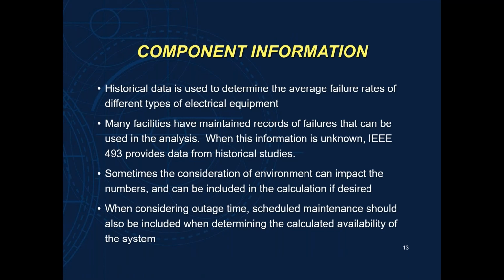Some bigger companies and companies that have a lot of records of their maintenance and their failures will have their own failure rates, say based on a circuit breaker. If they say it's a medium voltage circuit breaker, historically they fail this many times per year. And if they have that data documented, we can use that as part of their study, because that will take into account how well they maintain their equipment, how often they cycle their breakers, how often they do the things to improve their own reliability.